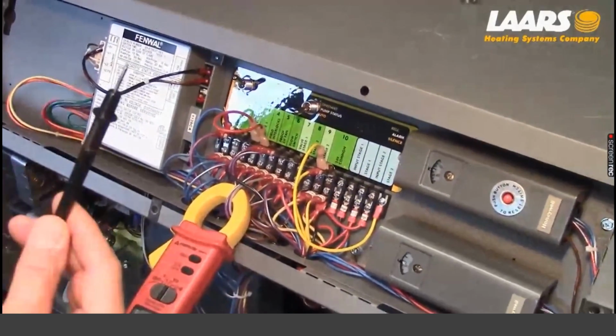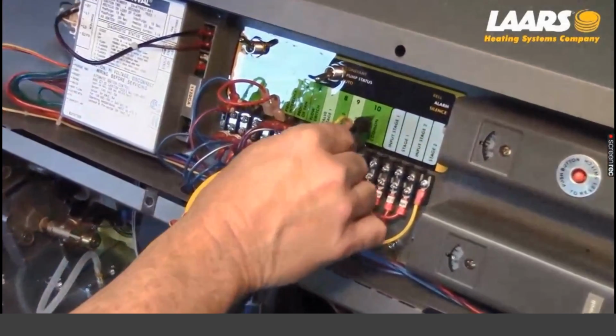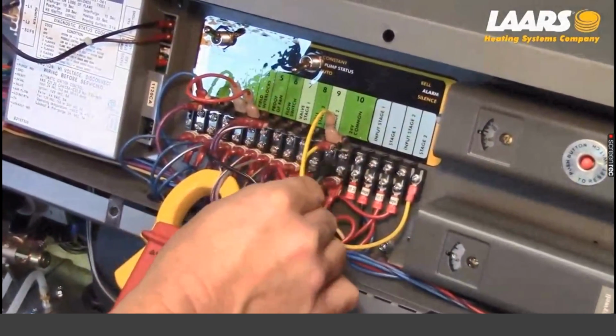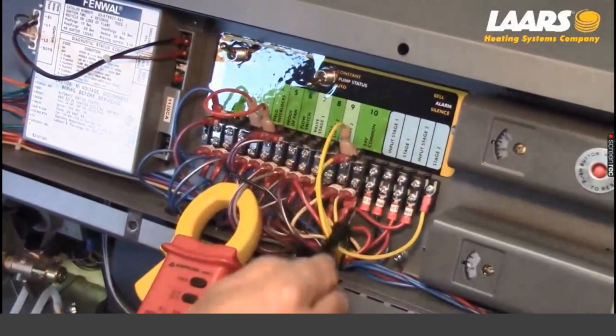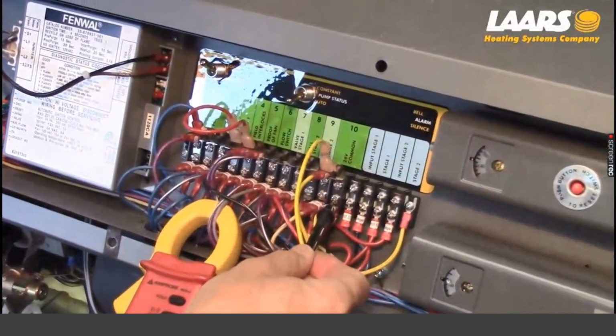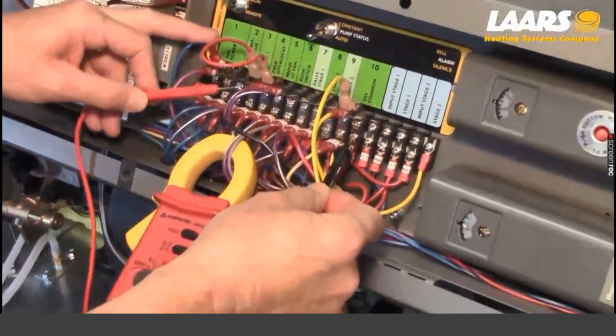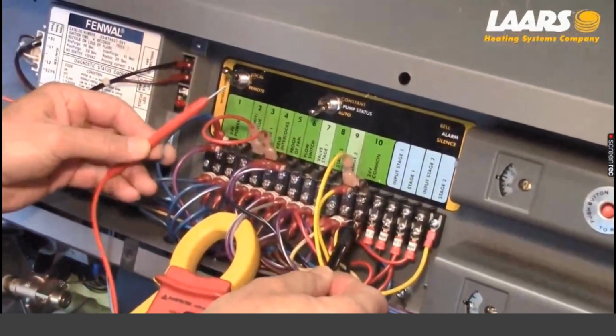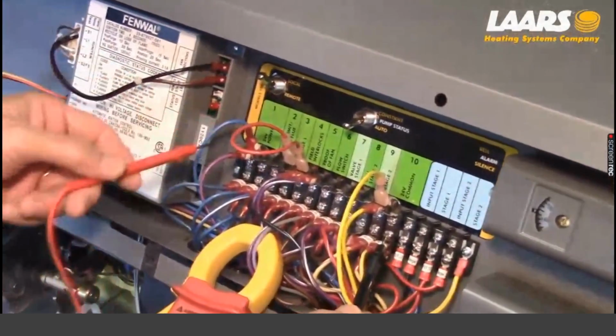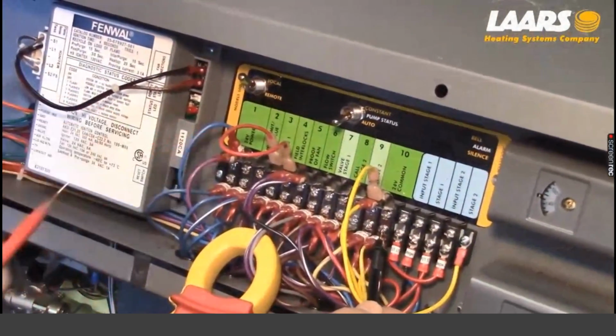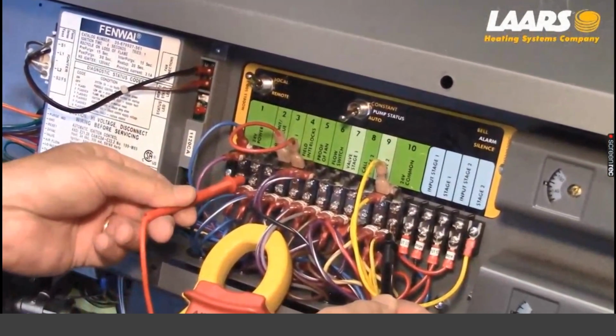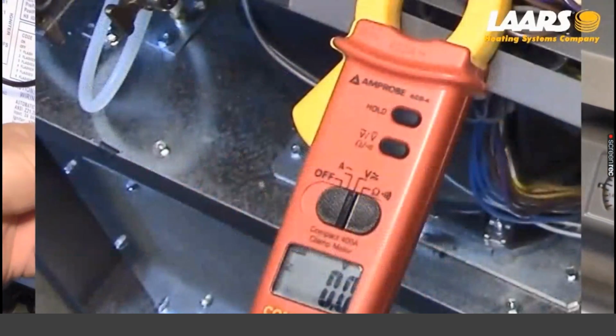So I'm going to start with one voltmeter lead and put it on 24 volt common here on terminal 10. Okay, now there are 2 sets of terminals for terminal 10, any one of those. The next one over here is 24 volt power. I'm going to come over to my 24 volt power, which is 2 terminals here as well, and I'm going to place it here, and as you can see, I do not have voltage.